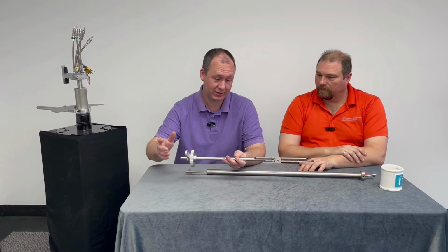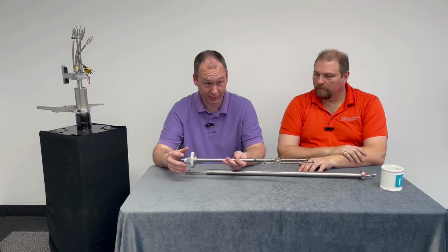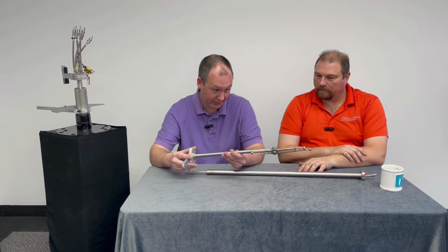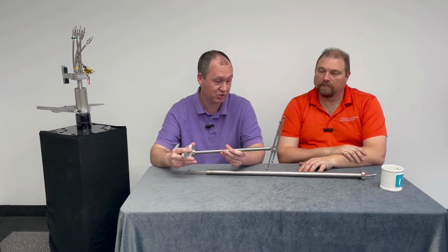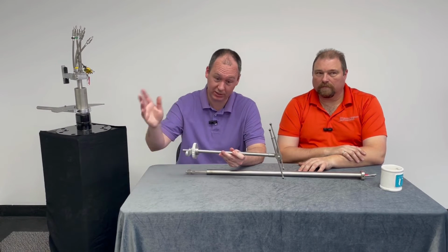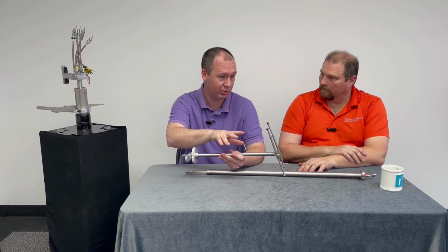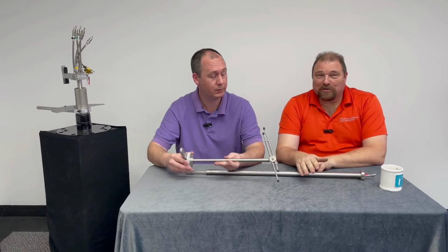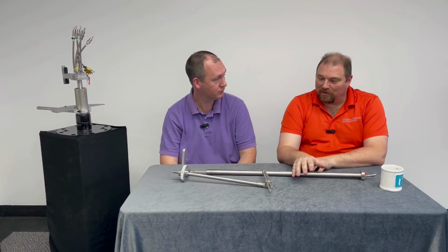So this probe samples isokinetically, meaning that it pulls the coal out at the same velocity as the coal is traveling. And with this probe, you put it in, and then periodically, every 15 seconds typically, you spin it, I think it's 22 degrees, and you rotate it through 16 different revolutions. And by doing that, you really cover the entire cross-section of the pipe as you sample out of each one of these nozzles.